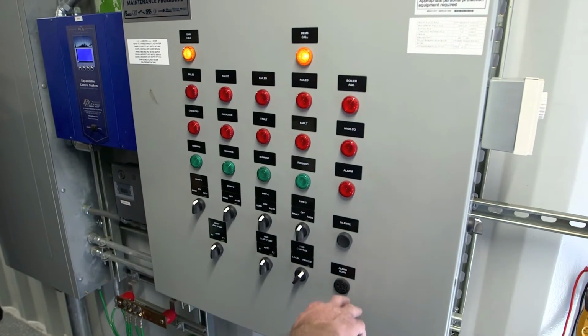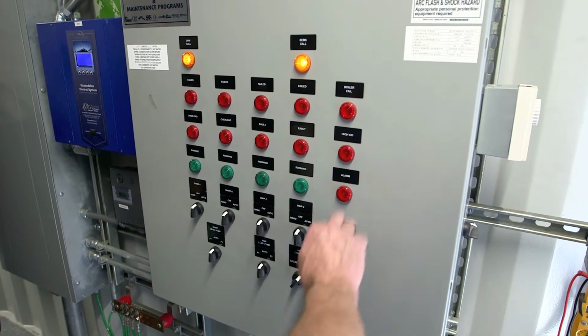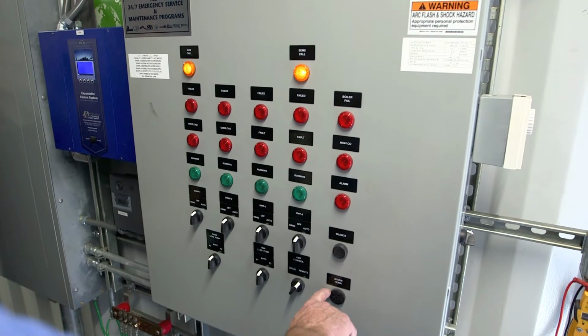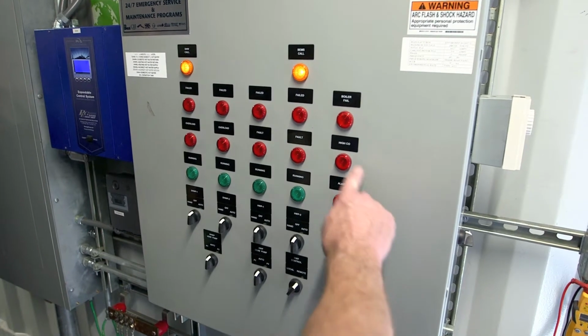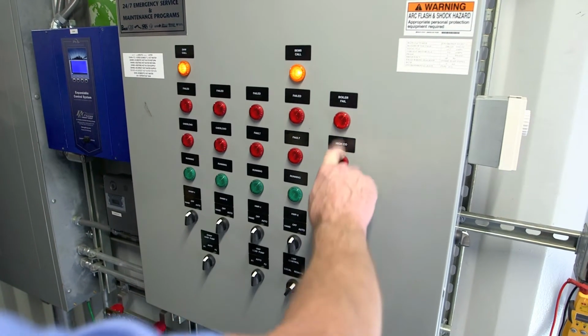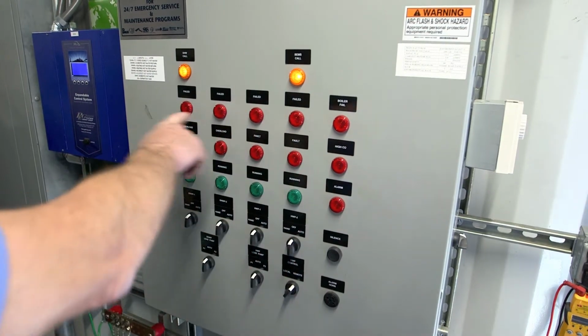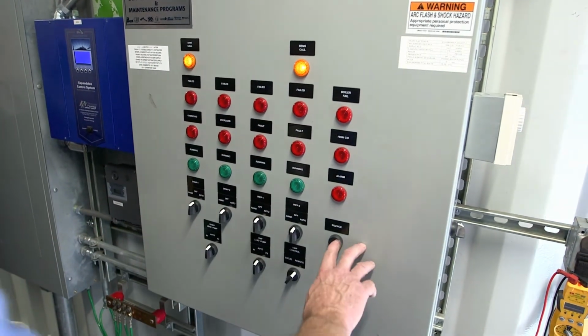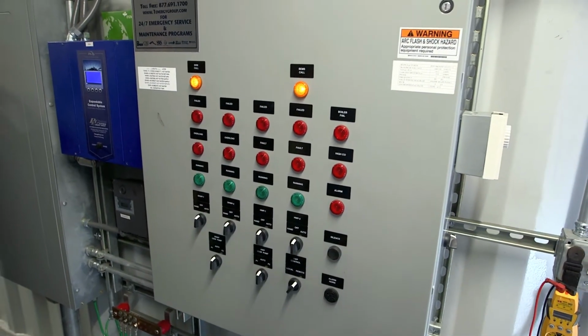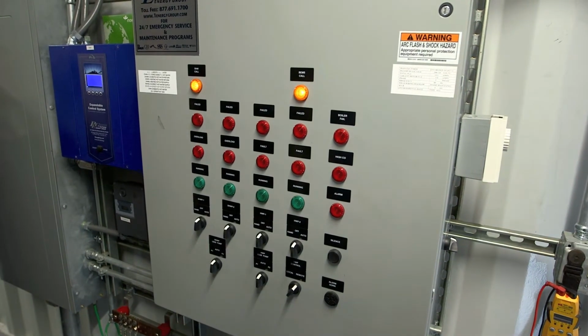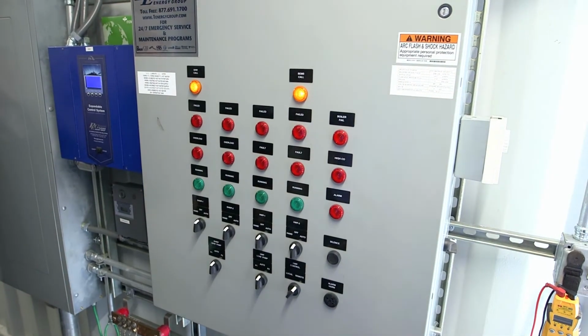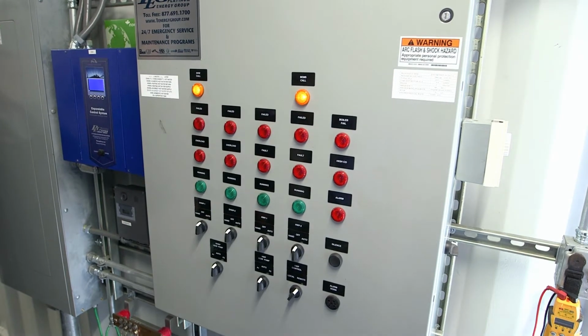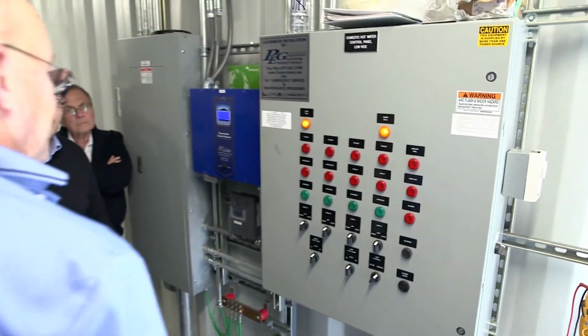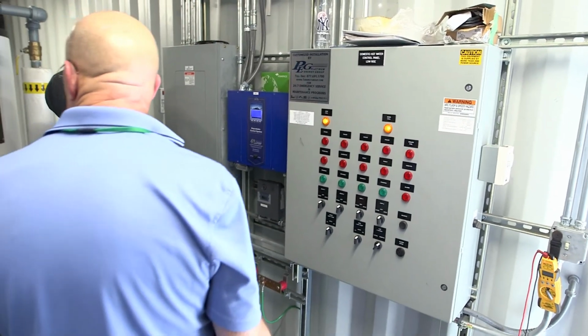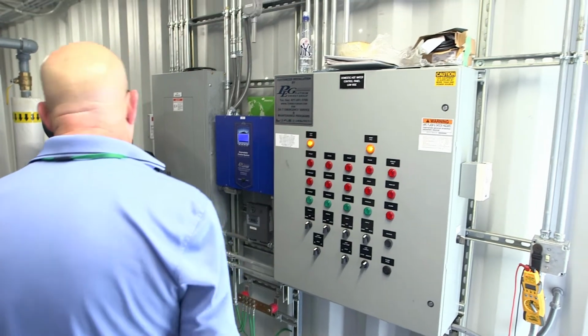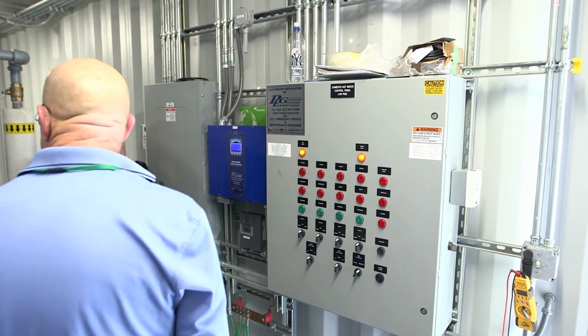If you come in and the alarm light will be on and this is singing, it's going to tell you high CO, the boiler failed, any one of the pumps failed. You can hit silence, so you can figure it out. It shuts the alarm off. You can try to go to hand to run the pumps. It's basically telling you the pump hasn't come on and you got to find out why. You can't find out why? We'll find out why.